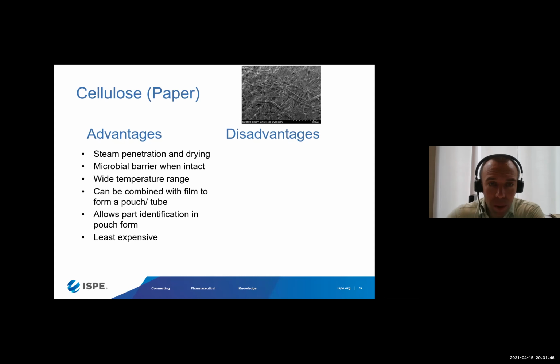But even so, the paper does have some advantages. This material's been used for sterilization wrapping for decades. It does allow good steam penetration. The aeration properties in the autoclave are good. The parts can be dried quite easily in the autoclave when wrapped with paper. The microbial barrier is also good, however, only when intact. So paper can be torn, especially during the sterilization process. It becomes saturated or wet, and we can have tearing through that process. It does become weak.